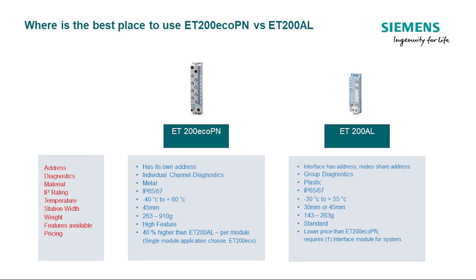Even though both products are I/O drops, they are very different products. The first big difference is that the ET200EcoPN has its own address, whereas the ET200AL has an interface module which holds the address. Each of the I/O drops are just like slots in a rack — they do not have individual drop addresses.